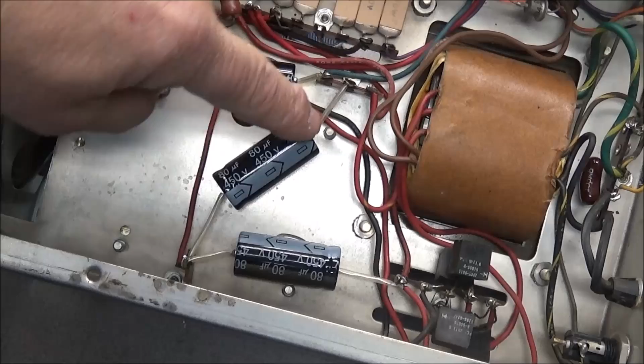Okay, we got all our new capacitors installed. Remember the big 80 microfarad cap set in here side by side and was bolted in. So what I've done was move this terminal strip that was here down to here, and I've already exposed a hole and bolted it in. When I bolt these terminal strips in, I put a star washer underneath of it, and that's just to ensure it gets a good ground. The ground lead is not used on this little terminal strip, but it's there in case we need it. But our two 80 microfarad capacitors come from ground and are in series, and then we pick up a center tap here. It goes here.